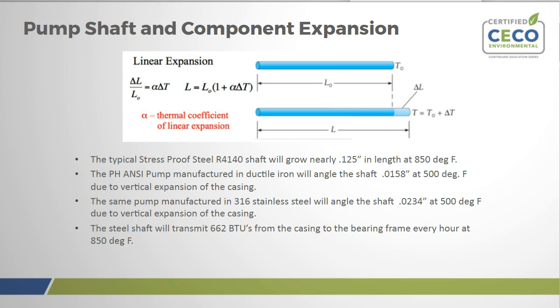You'll end up running the rotating portions into the stationary portions of the pump, unless those thermal displacements are taken into consideration during the design process, or they need to be negated. For an ANSI pump made of ductile iron, the angle of the shaft will be 0.0158 at 500 degrees due to the vertical expansion of the casing itself. So it's actually bending the shaft. It's causing the shaft to deflect.